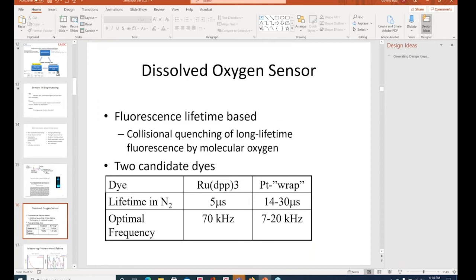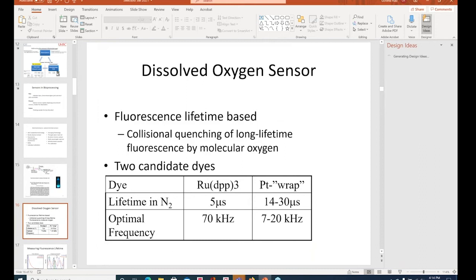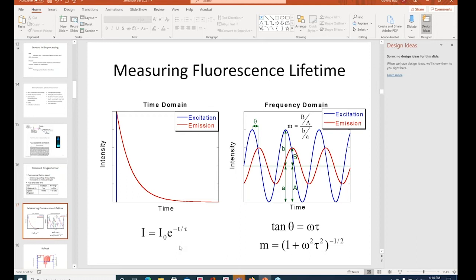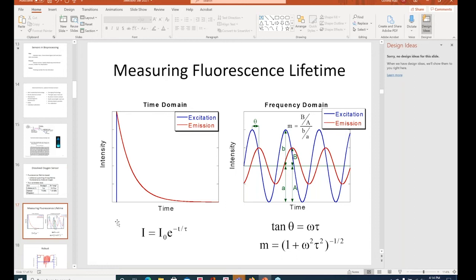Let's talk about the dissolved oxygen sensor. It's based on quenching of fluorescence. We experimented early in the days with a couple of different candidate dyes. And now the one that's being used is the ruthenium one. What's really enabled it is the fact that we were able to make a fluorescence lifetime measurement. Most of us are familiar with fluorescence intensity measurements, where you see this very pretty change in intensity and a different color that comes out. But fluorescence has several properties intrinsically associated with it, and one of which is the decay time. What happens when a molecule fluoresces is that the light intensity is absorbed and re-emitted with a finite exponential decay time.